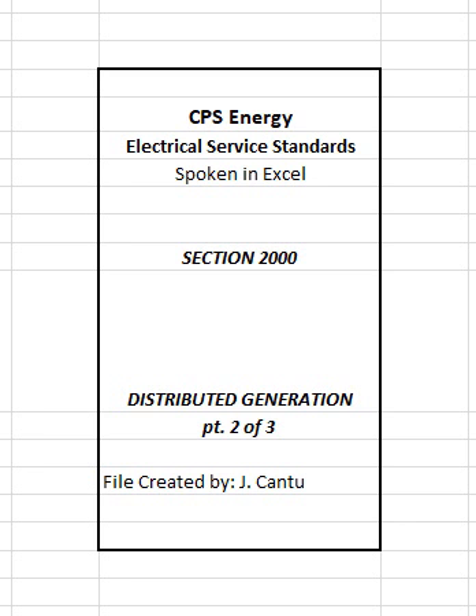F. PV AC meter disconnect. A disconnect furnished and installed by customer is required on the load side of inverters and before CPS Energy PV system metering equipment. The PV AC meter disconnect shall be located immediately adjacent to the PV system metering equipment and shall be readily accessible and capable of being locked in the open position. Refer to Figures 2002 and 2004. Note: An additional disconnect to isolate the PV meter will be required where the interconnection is made at a location remote from where the PV meter is to be located. G. Labeling of equipment. Customer shall be responsible for all labeling of DG facilities equipment as outlined in Figure 2006. Such labeling shall be in place at time of commissioning.